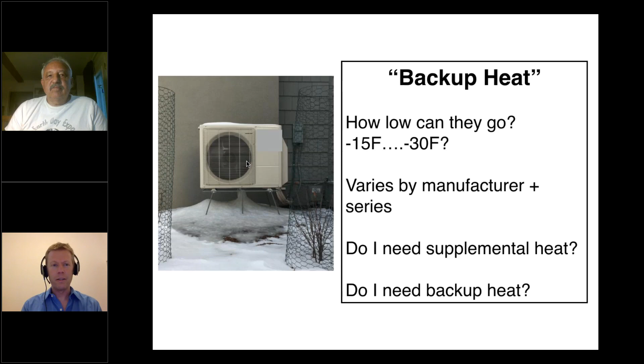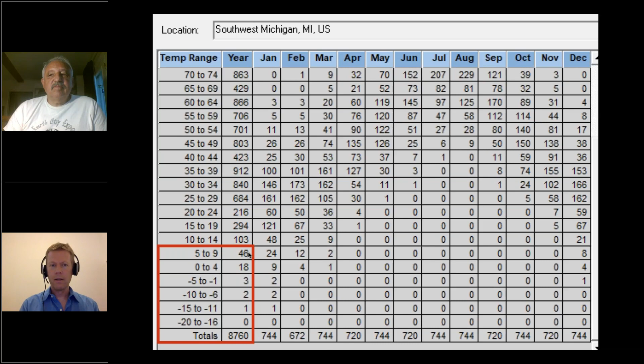Getting into the details of designing with these systems, you'll want to really dig into the typical hourly temperature bins from your heating and cooling load calculation software or other sources. This is for Southwest Michigan from the software that I use. In a typical year, you're going to find in most Michigan locations you have fewer than 100 hours with temperatures below 10 degrees. So even if you do need some electric resistance supplemental heat for your heat pump system, it's not a big overall energy or energy cost penalty to pay.